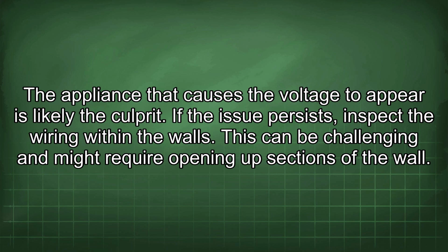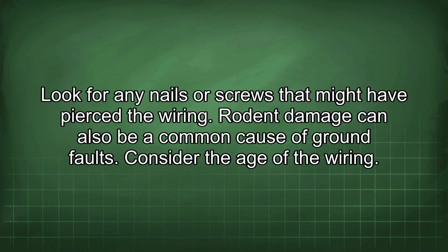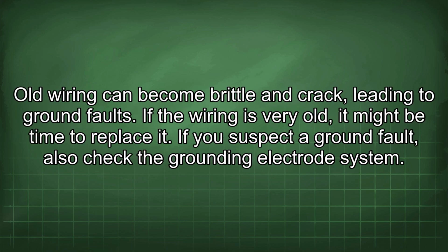If the issue persists, inspect the wiring within the walls. This can be challenging and might require opening up sections of the wall. Look for any nails or screws that might have pierced the wiring. Rodent damage can also be a common cause of ground faults. Consider the age of the wiring. Old wiring can become brittle and crack, leading to ground faults. If the wiring is very old, it might be time to replace it.